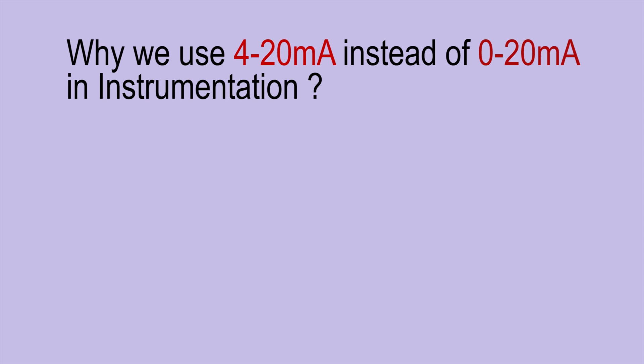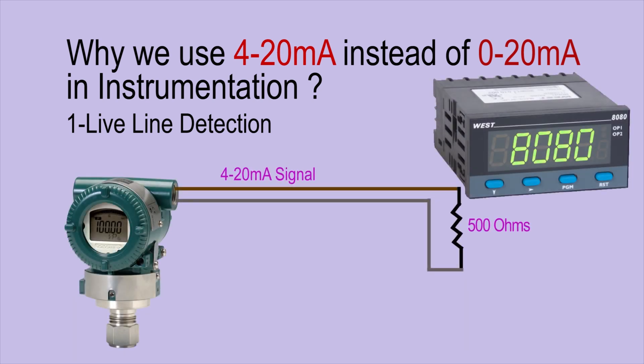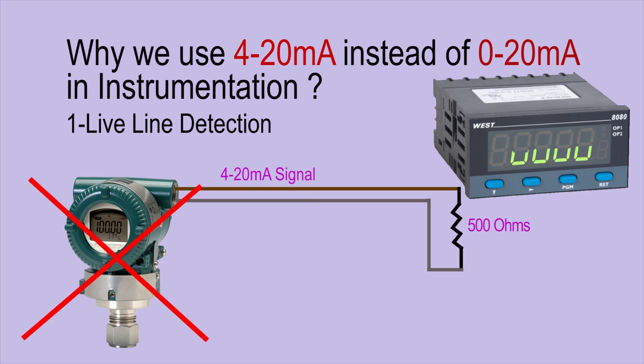Reason number one is live wire detection. Suppose we have a pressure transmitter connected to a pressure controller, and this pressure transmitter is giving a 4 to 20 milliamp output signal. Since the minimum signal is 4 milliamps, if the signal drops below 4 milliamps it indicates there is some issue with the transmitter or the wiring. For example, if the wire is broken or loose, or the transmitter itself malfunctions, the controller shows an error. So the 4 to 20 milliamp standard is very useful for detection of faulty wiring or transmitter malfunction.